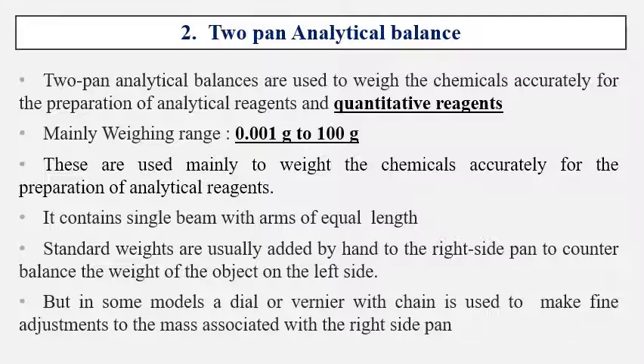The weighing range is from 0.001 gram to 100 grams. These are used mainly to weigh chemicals. It contains a single beam with arms of equal length. Standard weights are usually added by hand to the right-side pan to counterbalance the weight of the object on the left side. In some models a dial or vernier with chains is used to make fine adjustments.